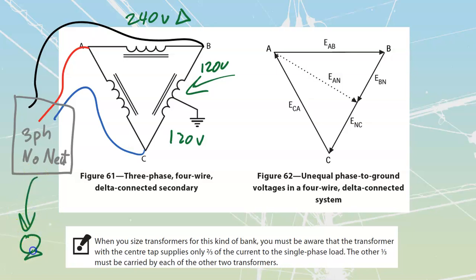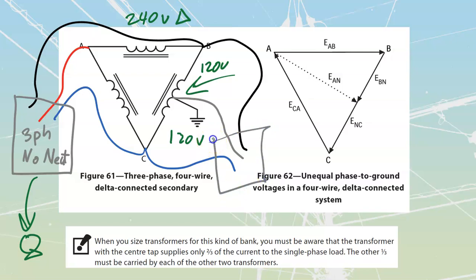You're going to have your motor loads, you're going to have 3-phase heaters, anything like that, that are going to get distributed out of there. We don't want a neutral in that panel because we don't want people fooling around trying to make single-phase connections inside of it. What you're also then going to be able to do is take your other lines, your B line and your C line, and your neutral that you have created by center tapping this transformer and grounding it down, are all going to get taken, and they're going to get put into another panel over here.